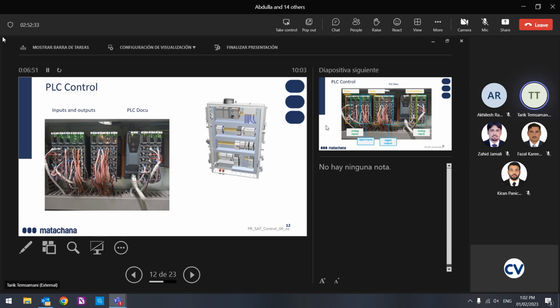If I had only one PLC and this sensor or this pressure switch is not reading well, I am not checking if it's reading well or not. I have to believe the value it gives me. But if I have two, controlled by different PLCs, I am always controlling this value. If one sensor fails, the other one does not fail and gives me different measurements, and I know there's a problem. So with the PLC, remember we always have one for control and one for documentation.